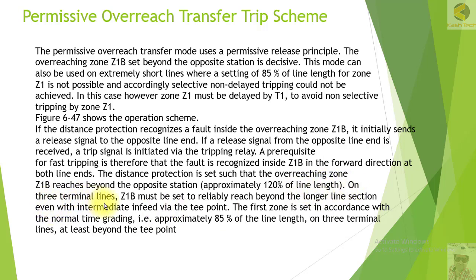On three terminal lines, Z1B must be set to reliably reach beyond the longer line section, even with the intermediate in-feed via the T point. The first zone is set in accordance with the normal time grading, that is approximately 85% of the line length, and on three terminal lines at least beyond the T point.